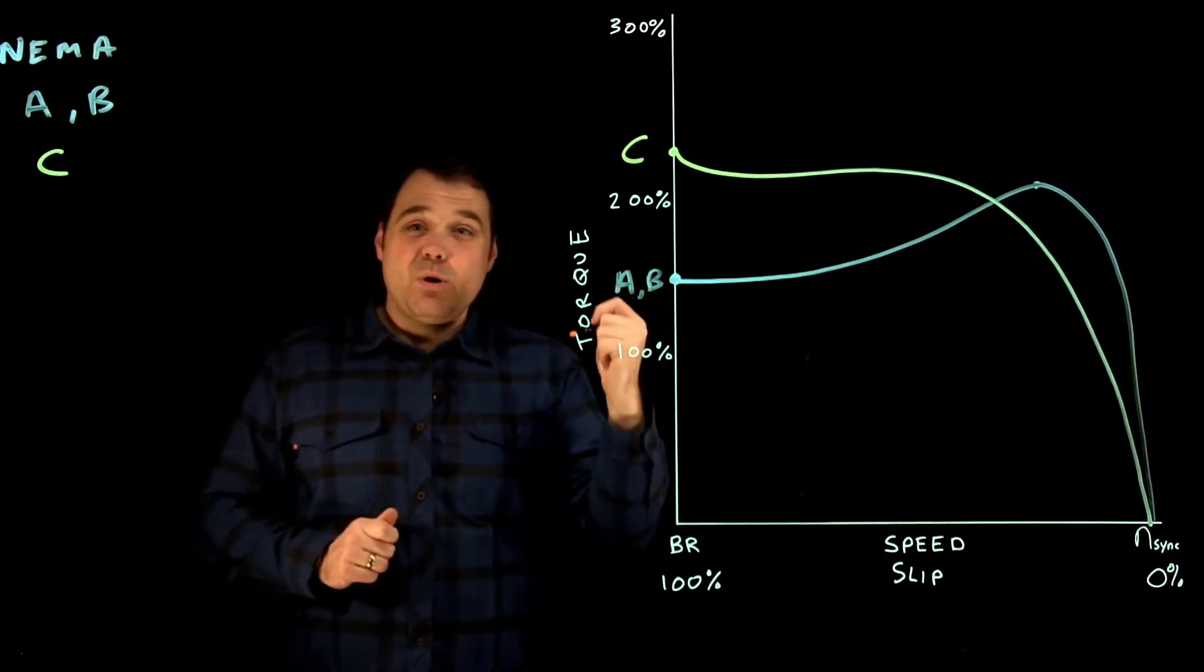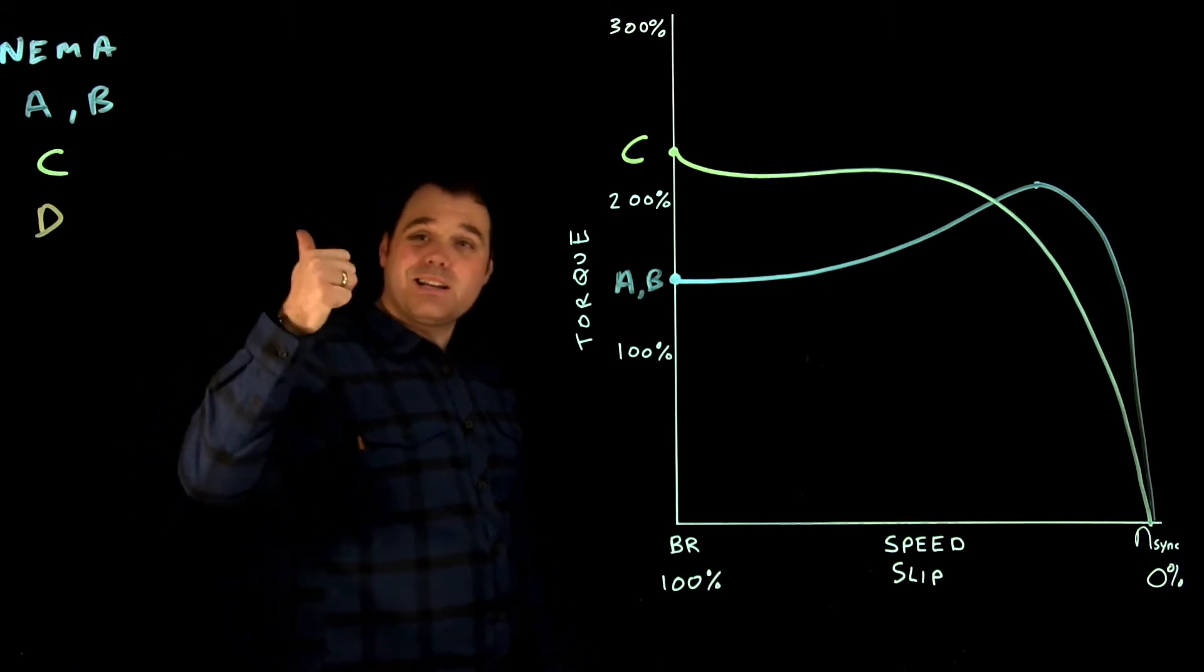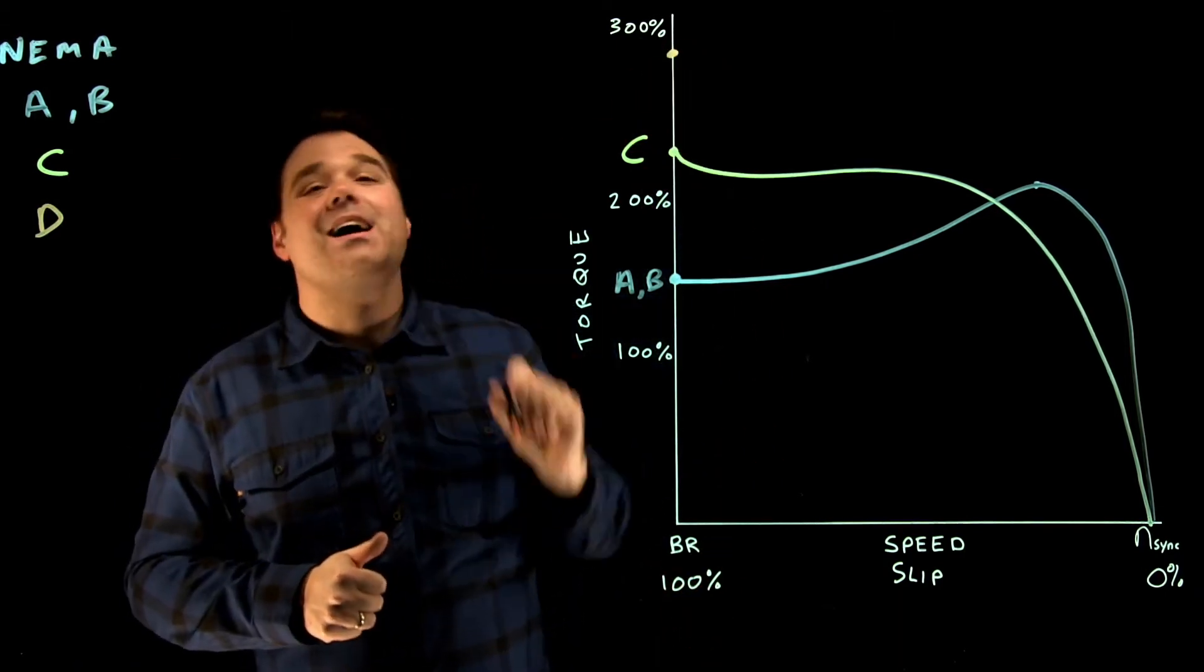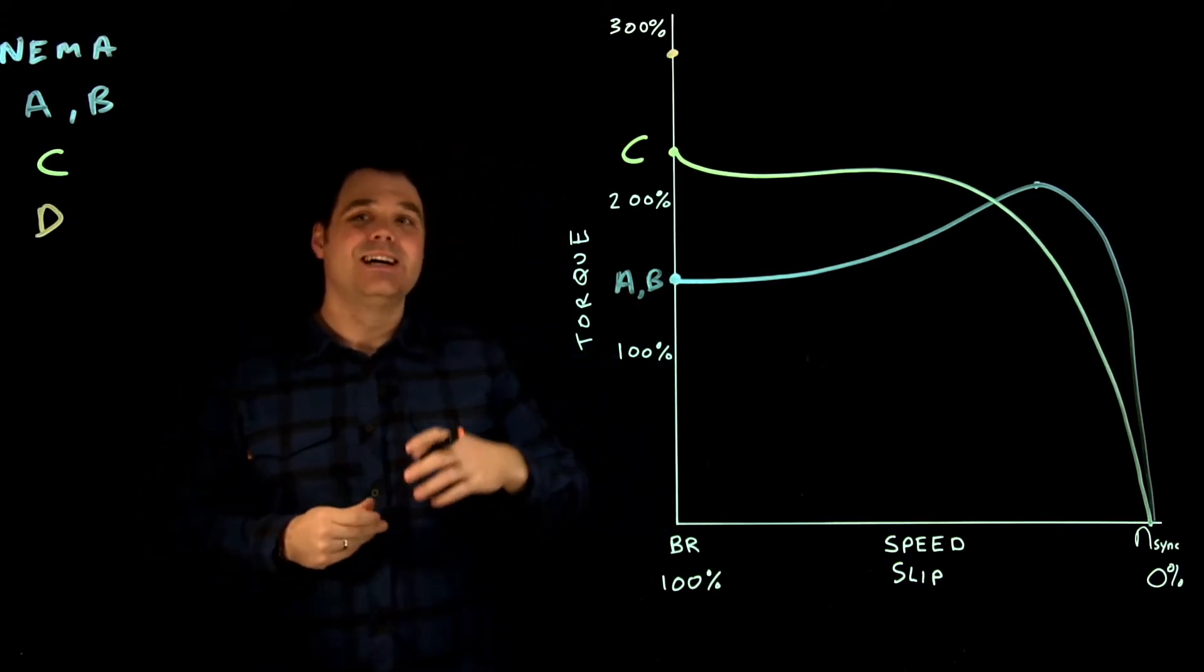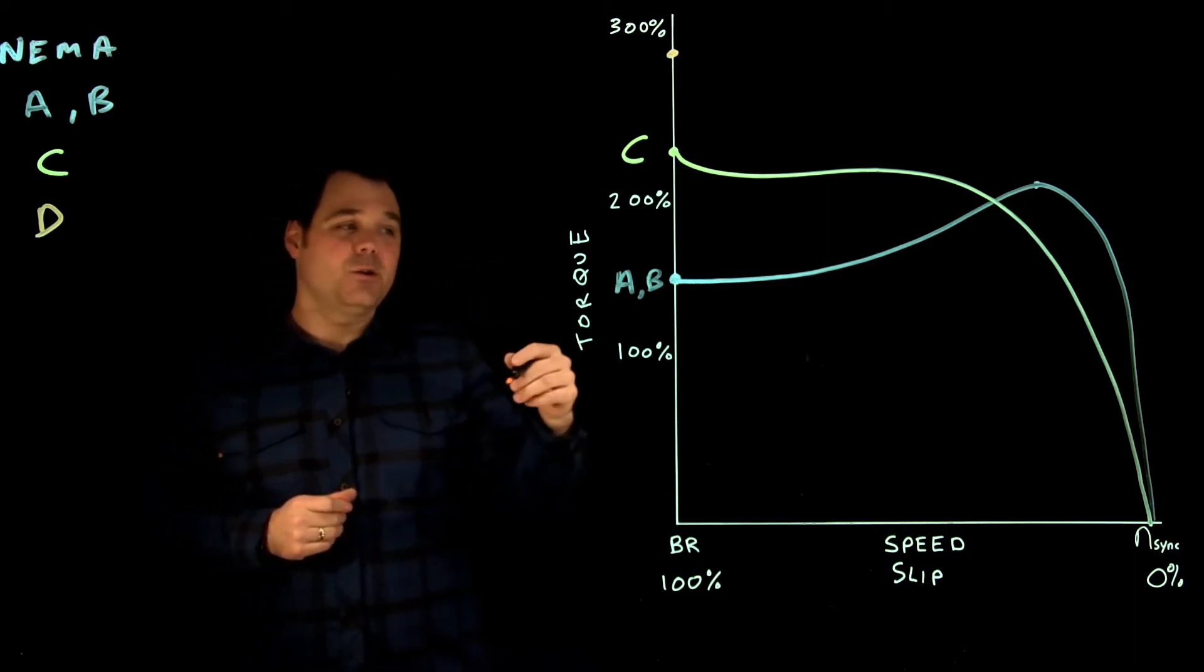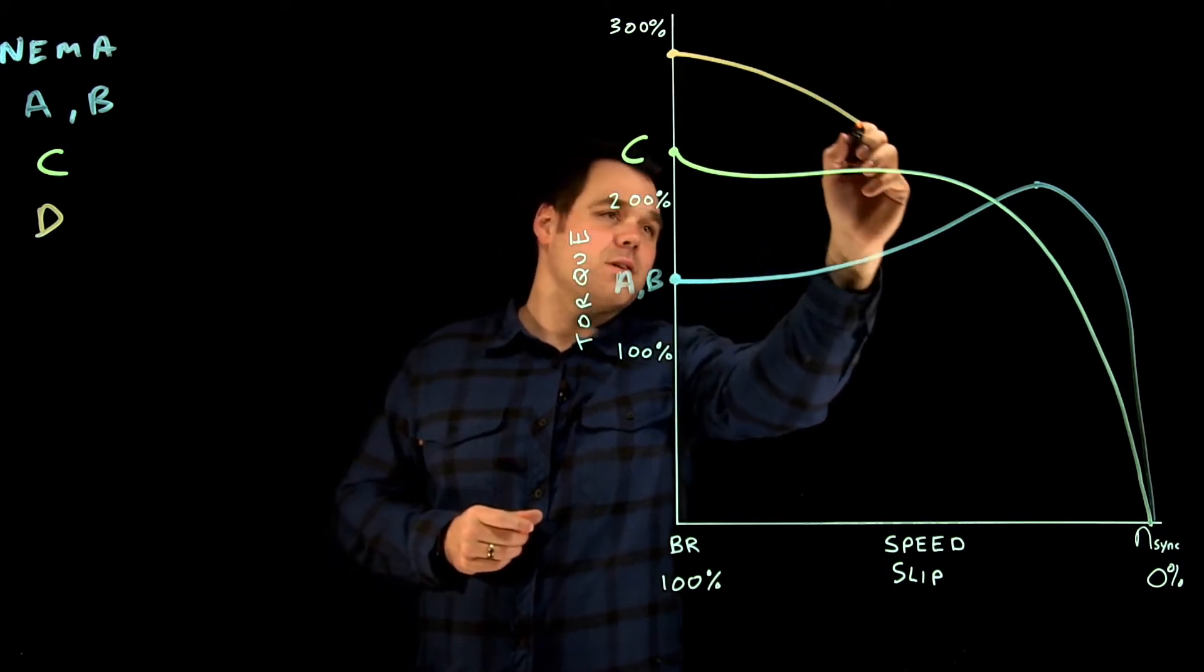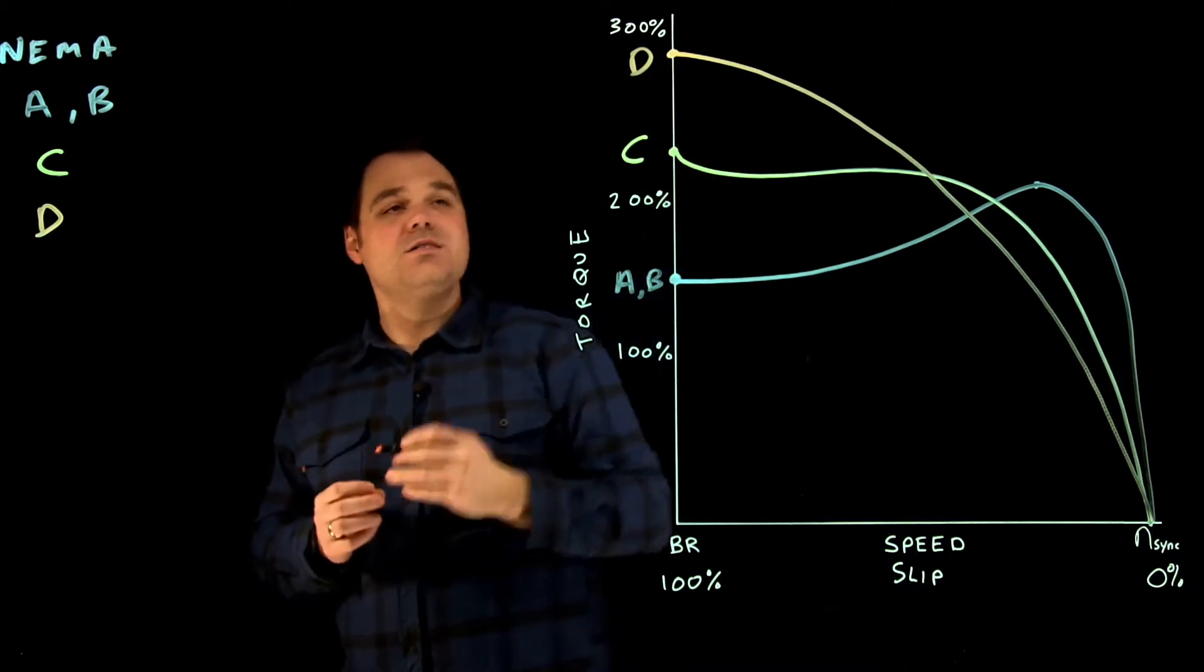Then with a NEMA rotor D. We like the D. The D has a very high starting torque, around 275%, and that's also where I get that peak torque. The problem with the D is it's very inefficient. So it's a great start, but it's a little bit inefficient. So this torque curve for the D ends up looking something like that.